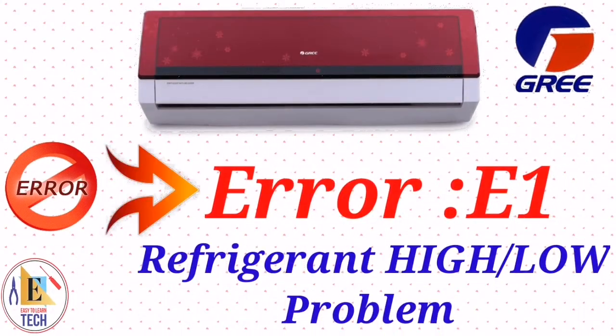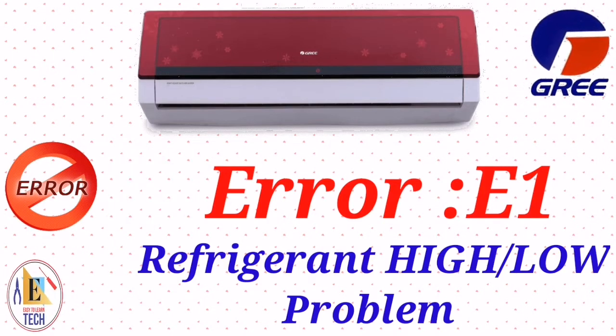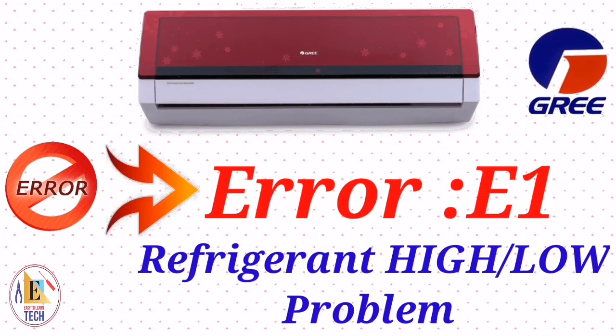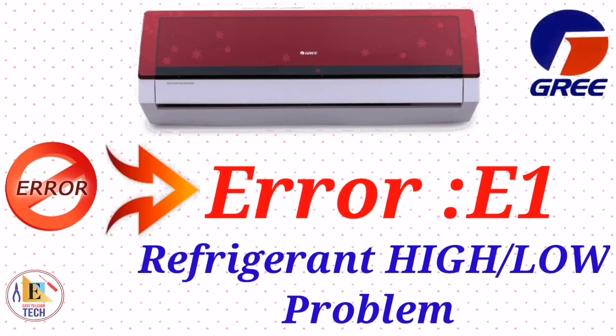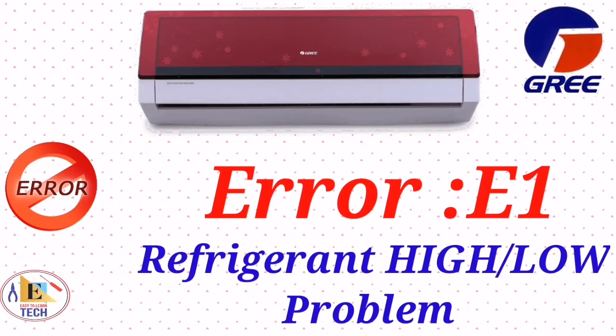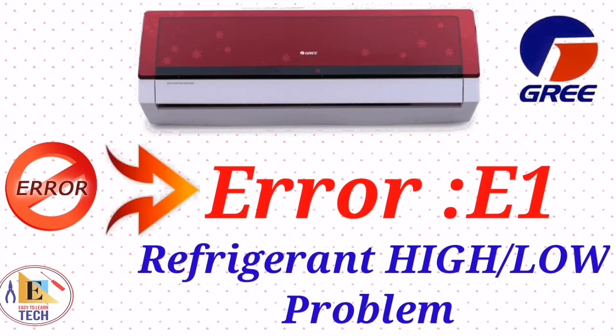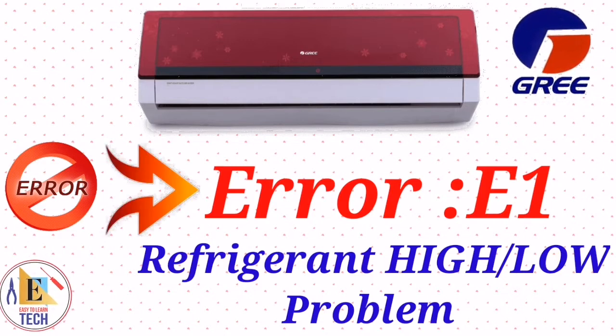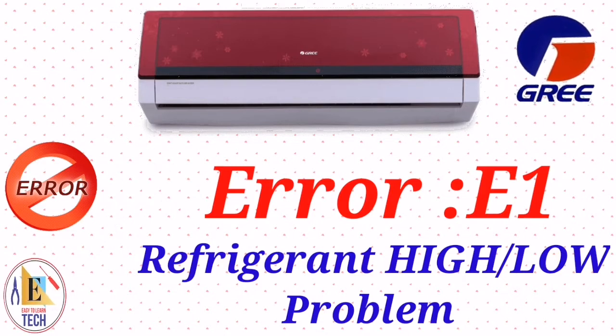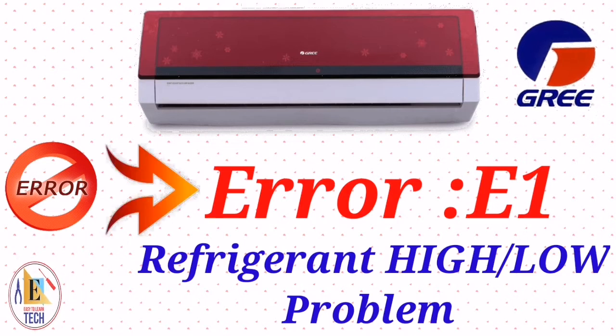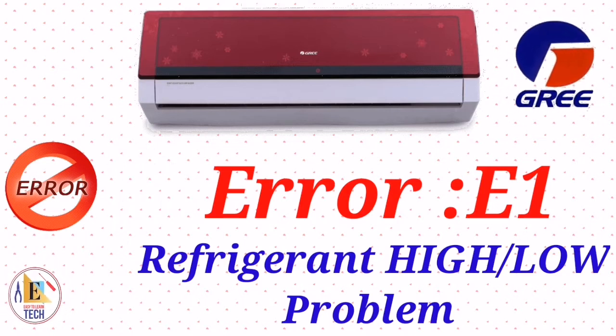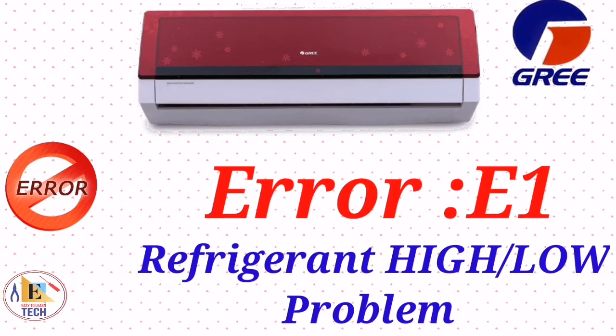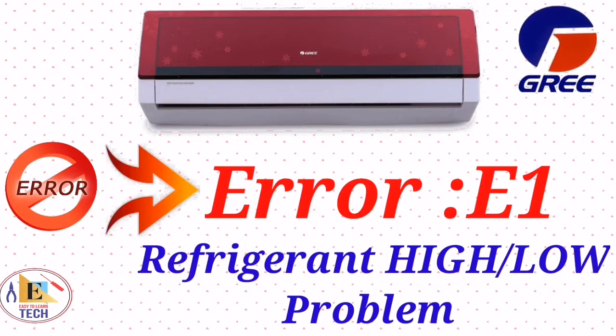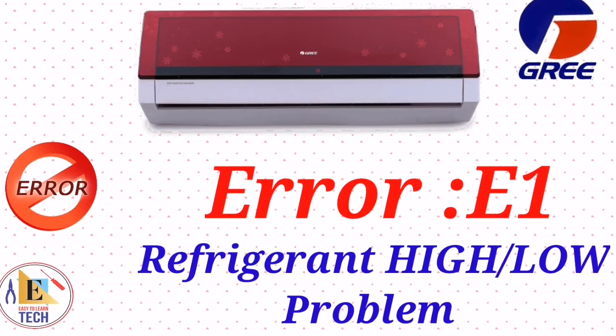See the next error code. When you see E1 in your display, it may be the issue of refrigerant. There must be a refrigerant high or low. When you get this error, directly you have to check the refrigerant in your system. You have to use the gauge and check the back pressure, and if the back pressure is low, it means there is a leakage in our refrigerant system. Find the leakage and fix the leakage. Then you have to charge the refrigerant according to the quantity required by the system.